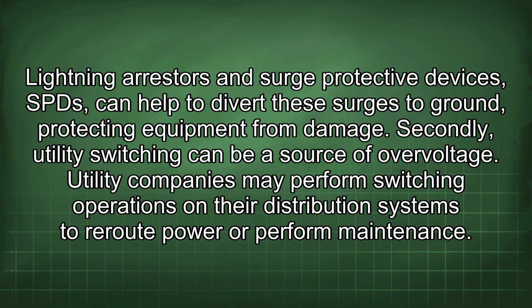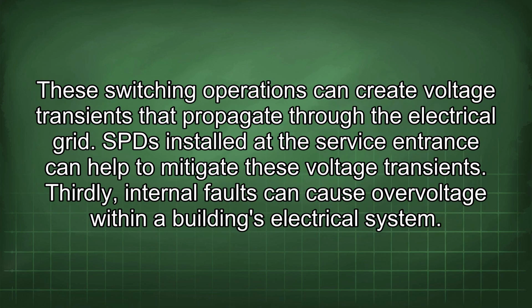Secondly, utility switching can be a source of overvoltage. Utility companies may perform switching operations on their distribution systems to reroute power or perform maintenance. These switching operations can create voltage transients that propagate through the electrical grid. An SPD installed at the service entrance can help to mitigate these voltage transients.